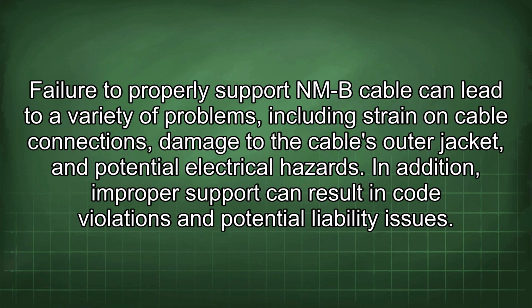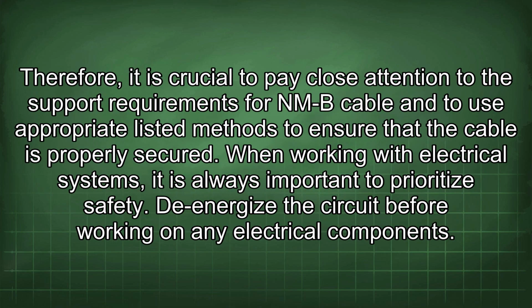Failure to properly support an NMB cable can lead to a variety of problems, including strain on cable connections, damage to the cable's outer jacket, and potential electrical hazards. In addition, improper support can result in code violations and potential liability issues. Therefore, it is crucial to pay close attention to the support requirements for NMB cable and to use appropriate listed methods to ensure that the cable is properly secured. When working with electrical systems, it is always important to prioritize safety. Always de-energize the circuit before working on any electrical components.